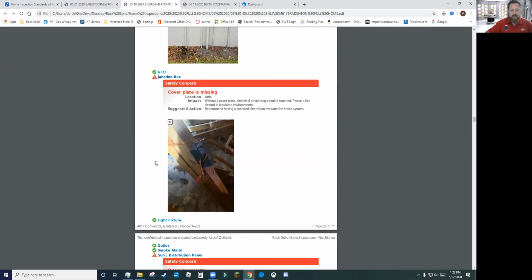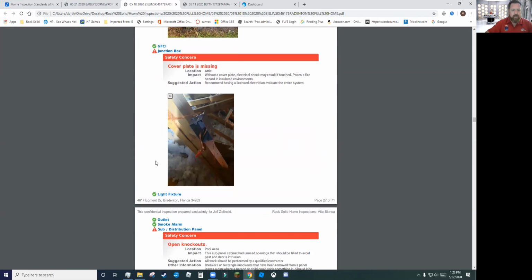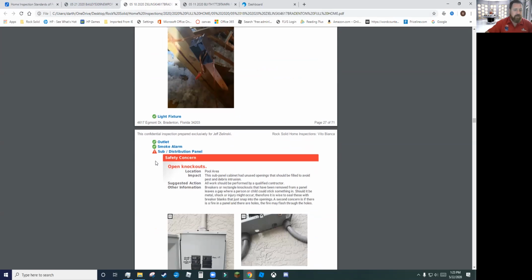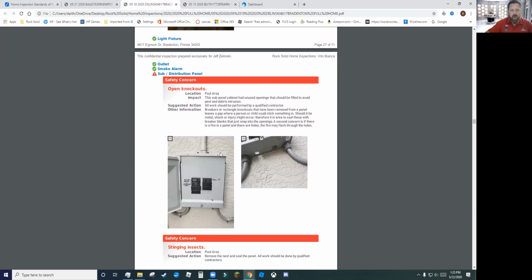They're very common in the attics—I see it a lot. Junction box missing, but at least it was up off the ground. Here we go, open knockouts. Even though it wasn't a circuit breaker that was missing a clamp—there's the clamps, you can see them right underneath the breakers. A 50-cent piece of plastic, pop it in, done.